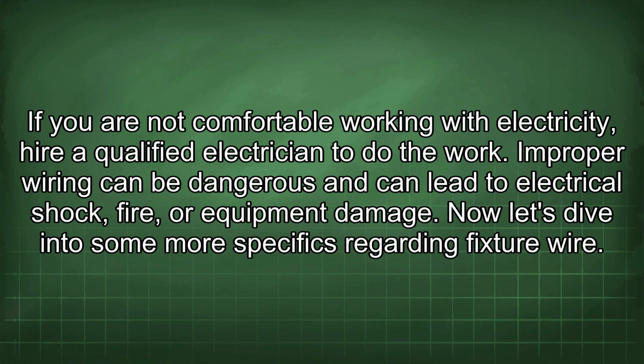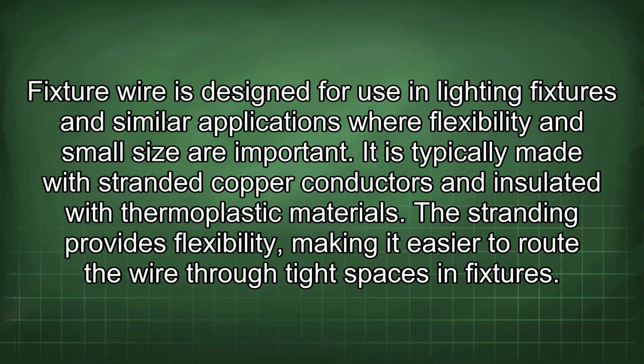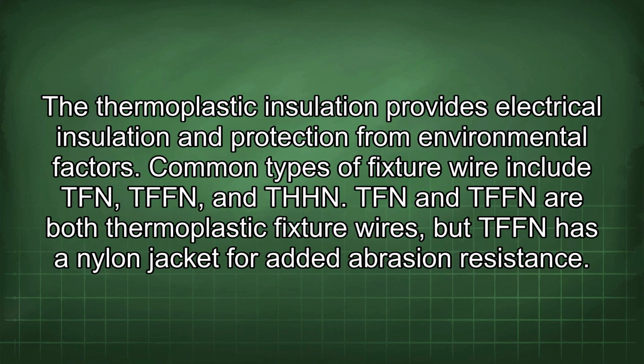Now let's dive into some more specifics regarding fixture wire. Fixture wire is designed for use in lighting fixtures and similar applications where flexibility and small size are important. It is typically made with stranded copper conductors and insulated with thermoplastic materials. The stranding provides flexibility, making it easier to route the wire through tight spaces and fixtures. The thermoplastic insulation provides electrical insulation and protection from environmental factors.